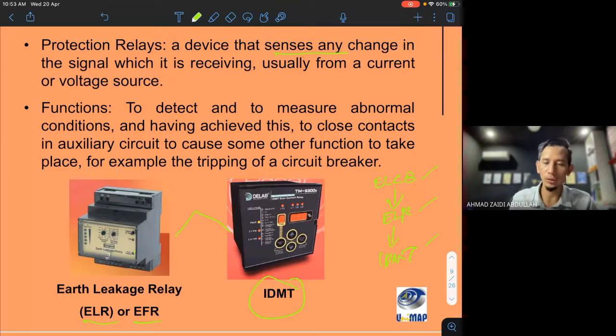So the function of the relay is to sense any changes in the signal it is receiving, usually from current or voltage. So that's why this component must come with the current transformer. It must connect to the CT. Let's say in your design schematic diagram you draw the ELR symbol but do not include the CT, so this is a wrong design lah.